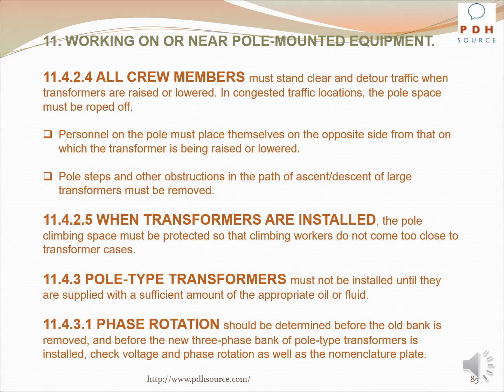When transformers are installed, the pole climbing space must be protected so that climbing workers do not come too close to transformer cases. Pole-type transformers must not be installed until they are supplied with a sufficient amount of the appropriate oil or fluid. Phase rotation should be determined before the old bank is removed and before the new three-phase bank of pole-type transformers is installed. Check voltage and phase rotation as well as the nomenclature plate.